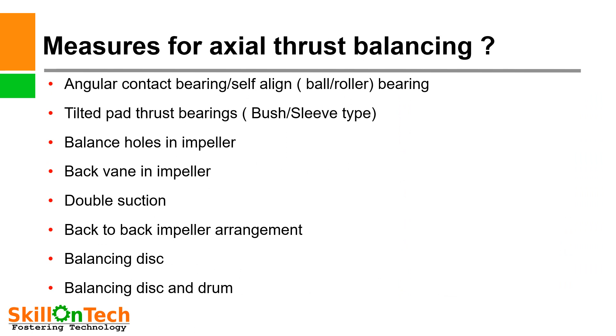Let us know what are the measures for axial thrust balancing in pumps and compressors. These include: angular contact bearings, self-aligning ball or roller bearings, tilted pad thrust bearings, bush and sleeve type bearings, and balance holes in impellers.